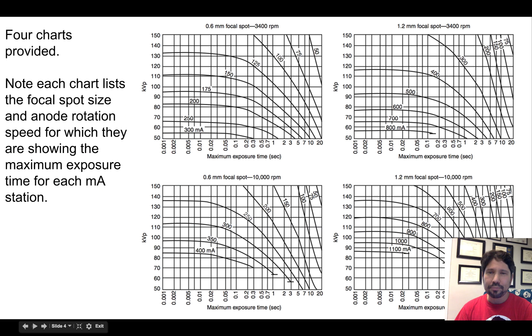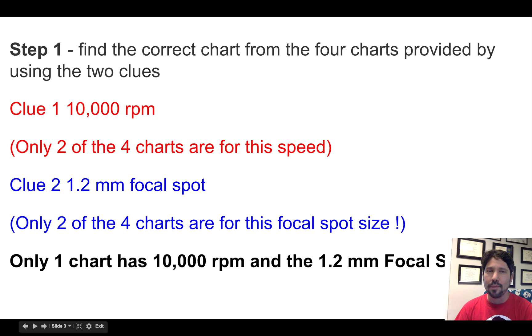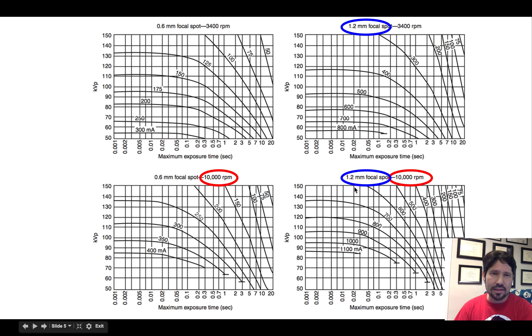And the question asks, find the chart that's talking about 10,000 RPM and 1.2 millimeter focal spot. So you need to read the chart as well as the problem, especially when they're multiple charts. So there's only one chart that has both the large focal spot and the fast spinning anode rotation speed. So we'll focus only on this chart as we move forward with this problem.